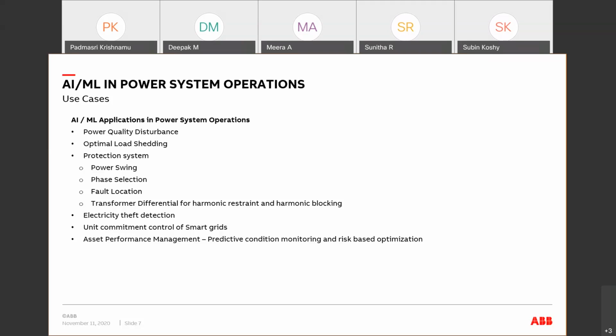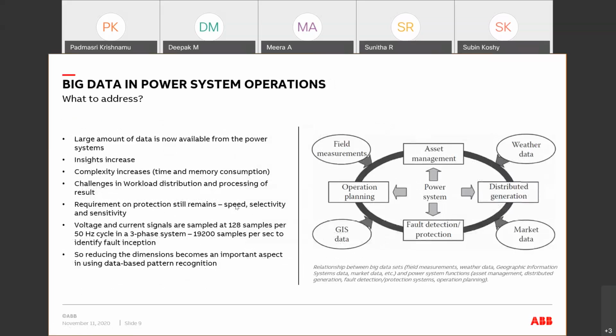Okay, then we go to... We perhaps will not spend too much time here. What is the kind of data you're talking about in differential protection? We are talking about voltage and current signals. They are sampled at 128 samples per 50 Hertz cycle in a three-phase system. That is, we are talking about 19,200 samples per second, and this is a three-phase system. So every second you are collecting this data, and it is subjected to analytics to identify the inrush versus the short circuit current. This is the quantum of data that we are talking about.